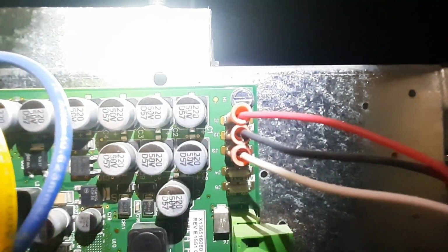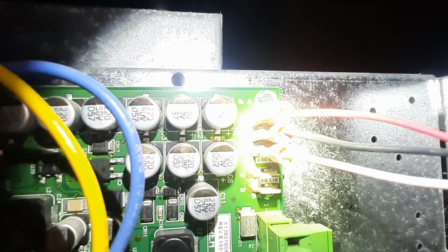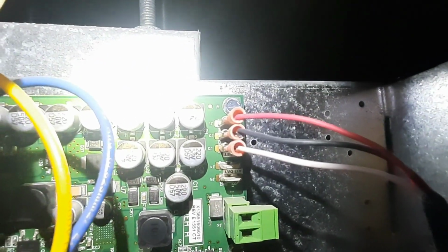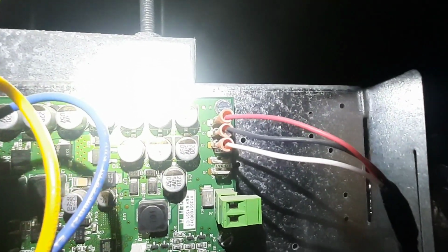So here we are. This is my gray thermostat wire here, and you can see you've got J1, 2, and 3, and if you look up in between there, it'll actually say set, zone, and ground, but it should be the same 1, 2, and 3, red, black, and white. We're just going to make sure all those match up at our thermostat. This is the board. There's not a whole lot more going on here. This pressure transducer is this 3-wire plug right there, and there's your actual pressure transducer. So there's a ring inside the inlet here that will read CFM. All of this has already been set up. Like I said, I can pull it up from the system, but that is the address back there, those 3 dials. So it looks like we are addressed, what is that, 001.